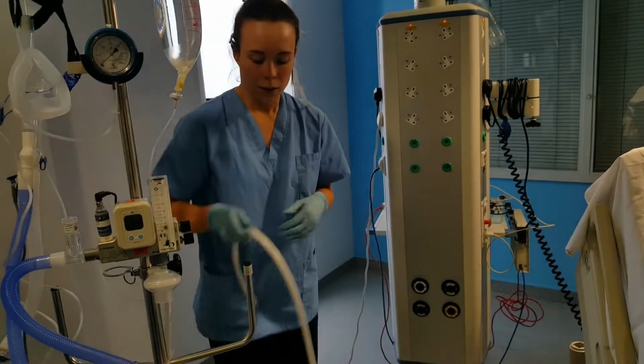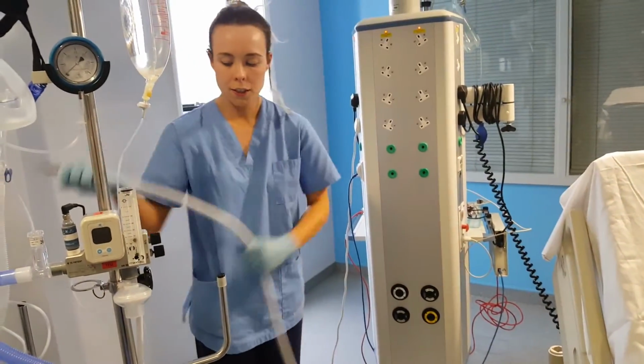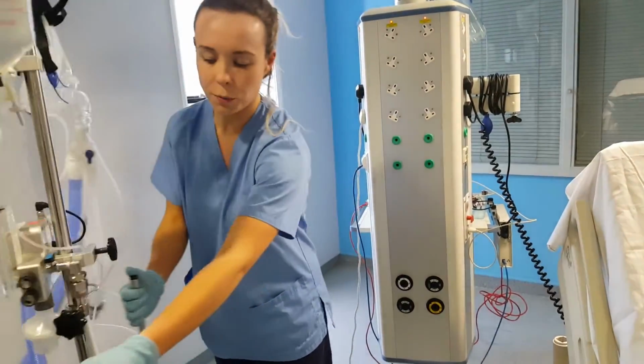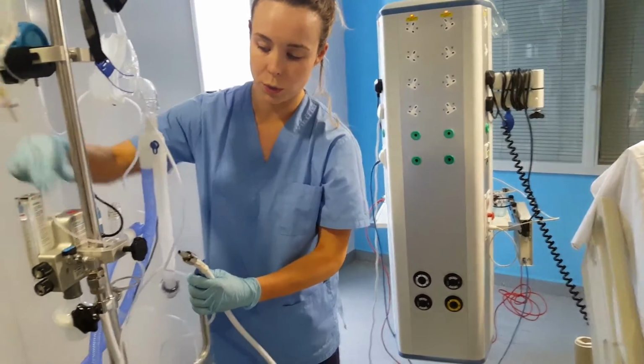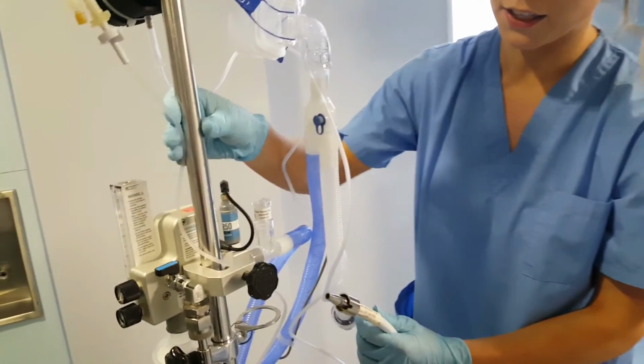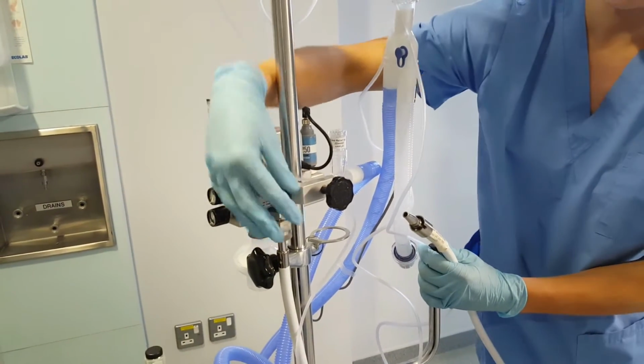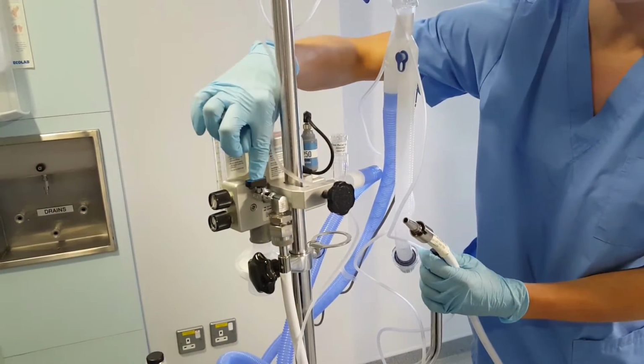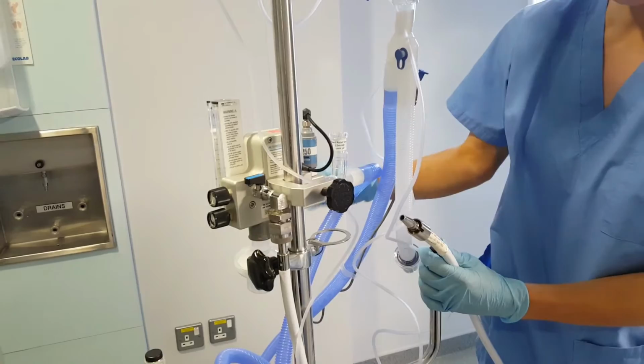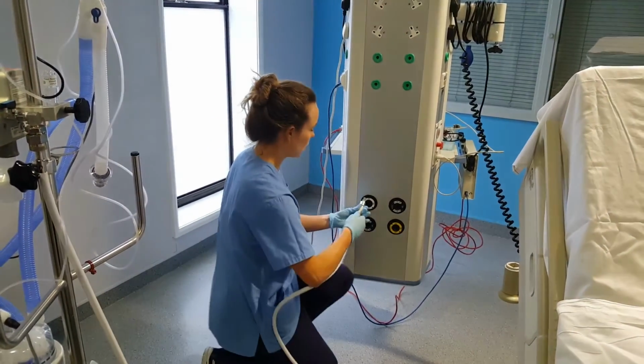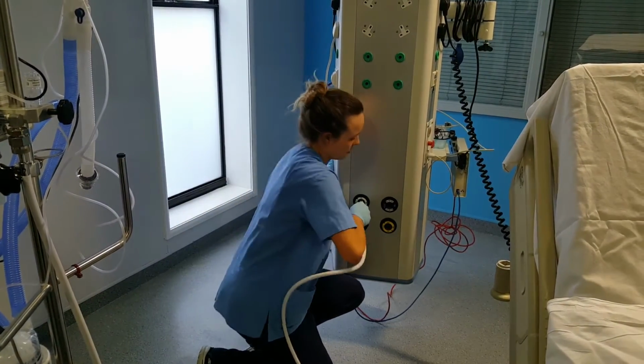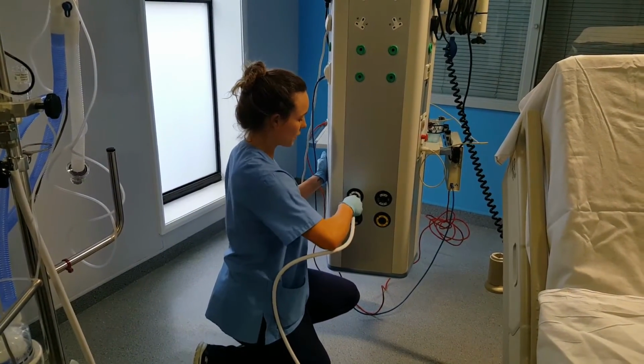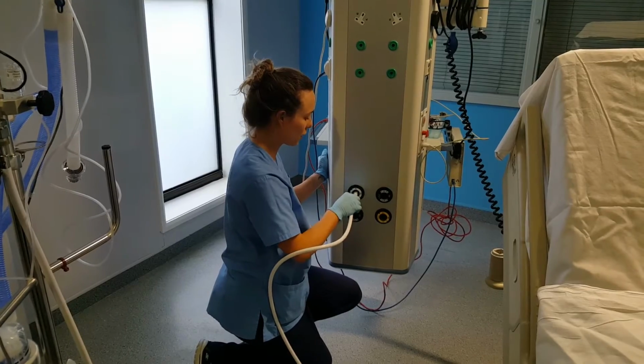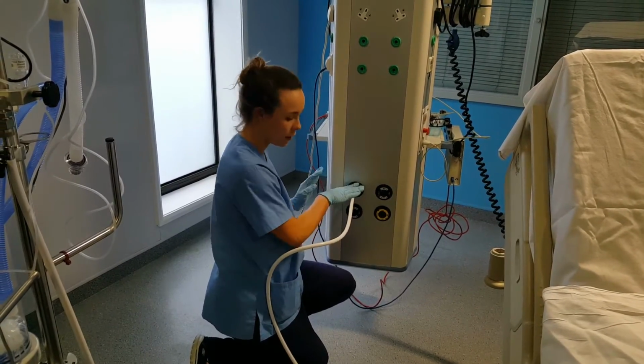There. So the next step, you connect your oxygen, which is coming from the back of the flow device that's connected to our external CPAP. So it's popping in here. There's our valve to turn it on, and it'll go through our circuit. So the first thing we'll do is connect it up. So you just click and make sure it's quite secure. Otherwise you won't be getting your oxygen flow. So give it a little pull, and if it doesn't come out, you know you're well connected.